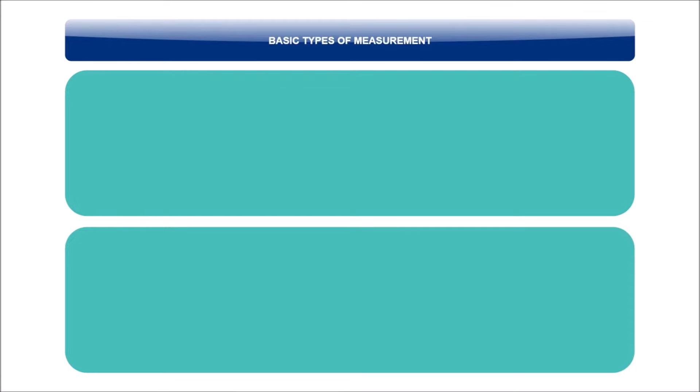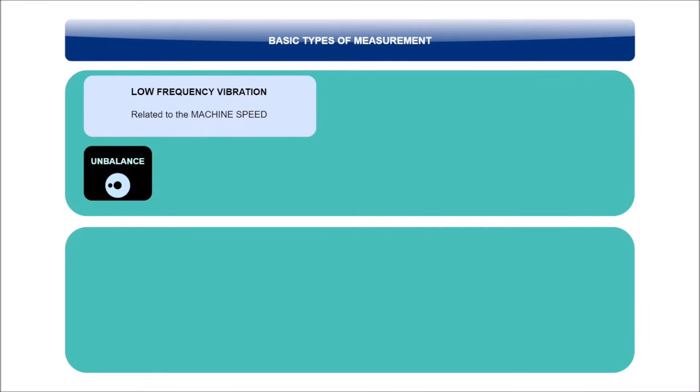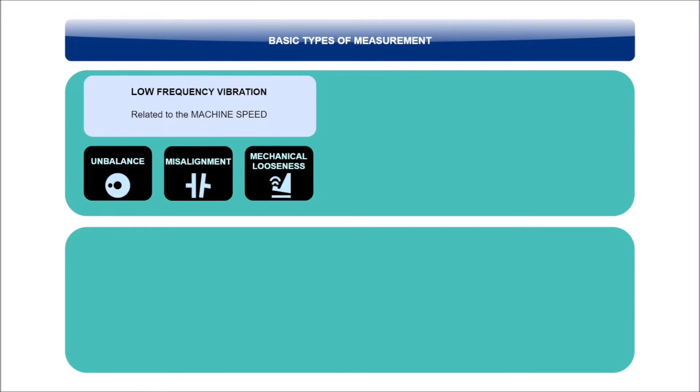All mechanical faults which are related to the speed of the machine, such as unbalance, misalignment, and mechanical looseness, are considered to be low frequency vibrations. These vibrations are measured as velocity in millimeters per second or inches per second. Maybe you are asking now how you can measure velocity with an acceleration sensor. With an acceleration sensor you can measure an acceleration value, but the meter, the analyzer, can convert the value to the velocity value. The most common frequency range of this measurement is 10 to 1000 Hz.